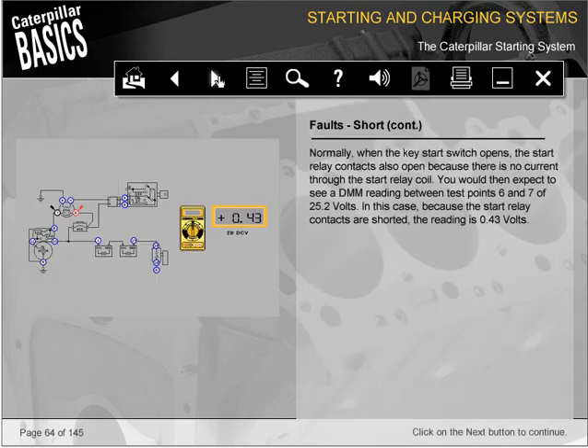Normally, when the key start switch opens, the start relay contacts also open because there is no current through the start relay coil. You would then expect to see a DMM reading between test points 6 and 7 of 25.2 volts. In this case, because the start relay contacts are shorted, the reading is 0.43 volts.